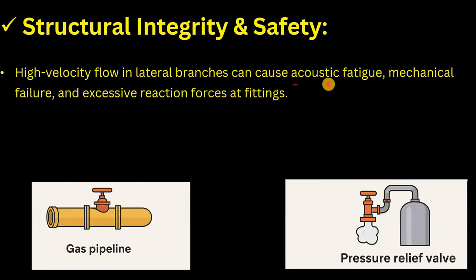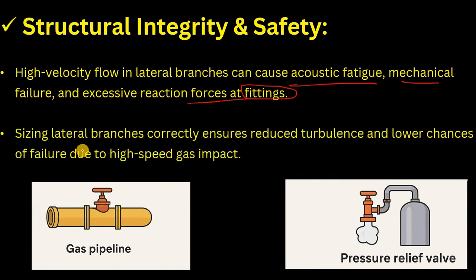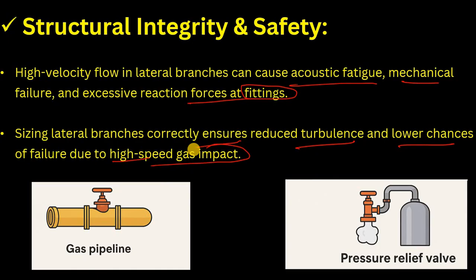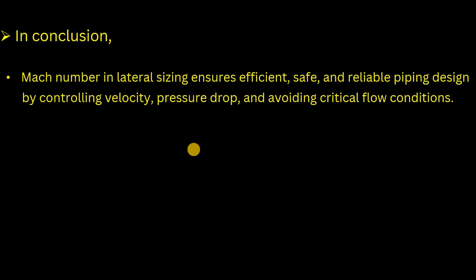High velocity flow in lateral branches can cause acoustic failure, mechanical failure, and excessive reaction forces at fittings. Sizing lateral branches correctly ensures reduced turbulence and lower chances of failure due to high-speed gas impact. When doing line sizing for gas, always check the Mach number — if it approaches or exceeds one, acoustic and mechanical failure can damage fittings and ultimately the plant.